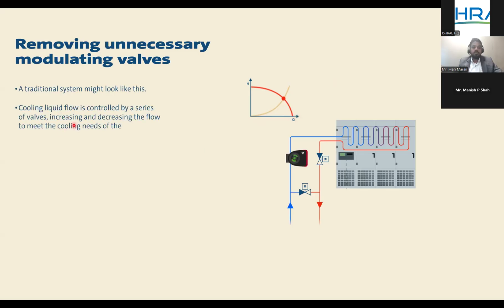So the cooling liquid flow is controlled by a series of valves, increasing and decreasing the flow to meet the cooling needs. As I said, this is a typical view of one particular load. Let's say this is a supply line from your secondary or primary system. The chilled water is getting into the coil, and this is the return line where we have a modulating valve which modulates the flow. The control is reliable. We achieve the temperature that we have to maintain, but at a cost, as I said. It comes with an additional cost, and we want to bring savings by changing the way we approach the system.